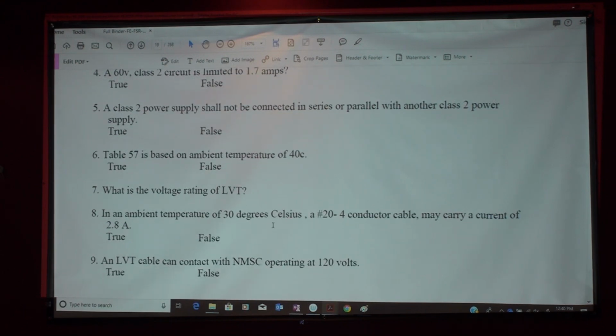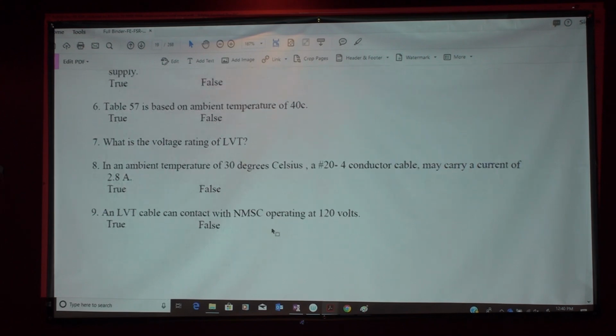Next question, what is the voltage rating of LVT? Your turn dear. 30 volts. 30 volts. Good job. Next question, if an ambient temperature of 30 degrees C, in an ambient of 30, on number 20, what conductor cable will carry 2.8 amps, true or false? So you went to table 57 there. What's your answer on that chart? I got true. But let's do the math together. Go to table 57, look for number 20 in a cable column and tell me how many amps you see.